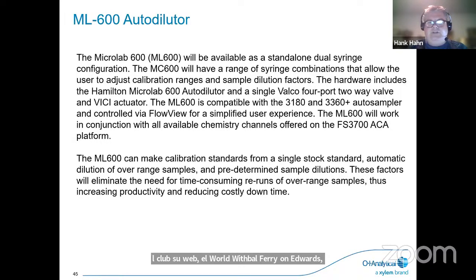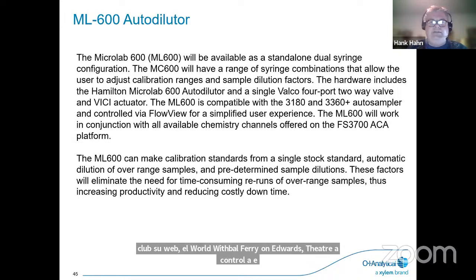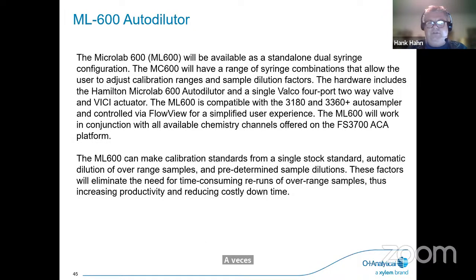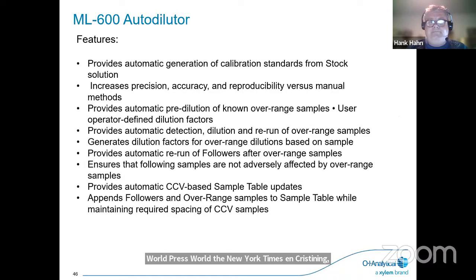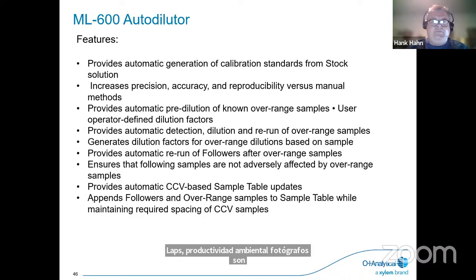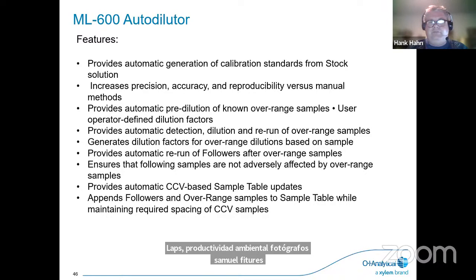It can make sample calibration standards as well from a single stock standard. And that's really what a lot of folks appreciate about this. Automated dilution of overrange samples and predetermined sample dilutions. And these factors will eliminate the need for time-consuming reruns of overrange samples, increasing your lab's productivity and reducing costly downtime for the clients. Some of the features, as mentioned: it provides generation of calibration standards, increases precision, accuracy, and reproducibility versus manual. Provides automated pre-dilution of known overrange samples.